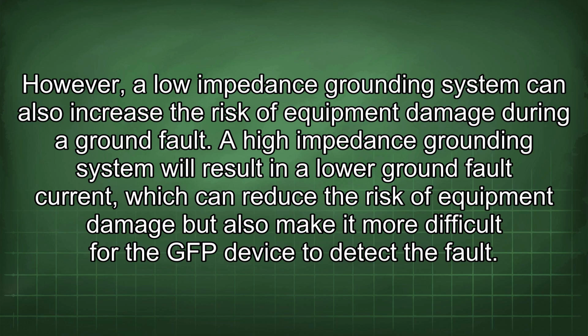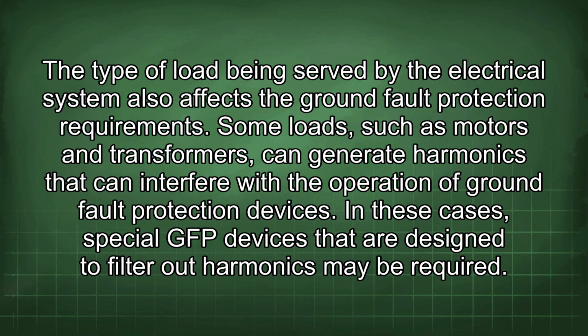A high impedance grounding system will result in a lower ground fault current, which can reduce the risk of equipment damage but also make it more difficult for the GFP device to detect the fault. The type of load being served by the electrical system also affects the ground fault protection requirements. Some loads, such as motors and transformers, can generate harmonics that can interfere with the operation of ground fault protection devices. In these cases, special GFP devices that are designed to filter out harmonics may be required.